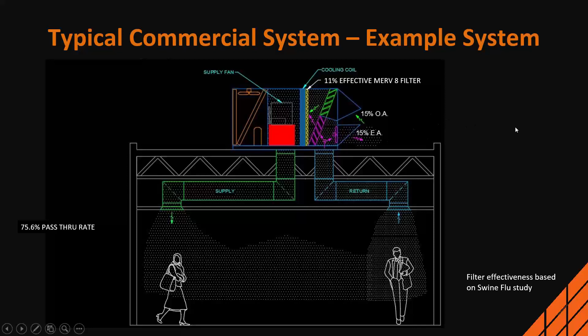So the first recommendation is to increase the ventilation rate. The goal here is to dilute the indoor contaminants. The codes over the years were primarily focused on energy. And as such, in 2006 in a common office we were looking at 20 CFM per person, and now we're down to about 5 CFM plus 0.06 per square foot.